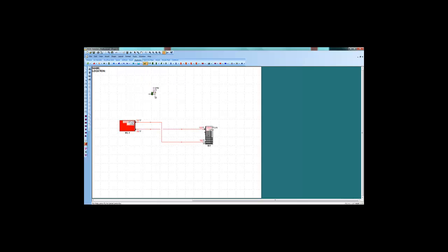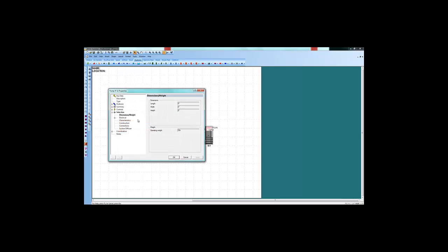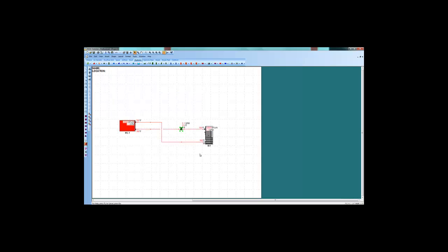The next step is to add a pump. Because the pump is in the pipe, it knows its place in the world and it starts to size itself. Next, we hit the equipment selection button. The program automatically provides a pump selection. Next, we insert pipe sizes and other components as necessary to finish out the design.